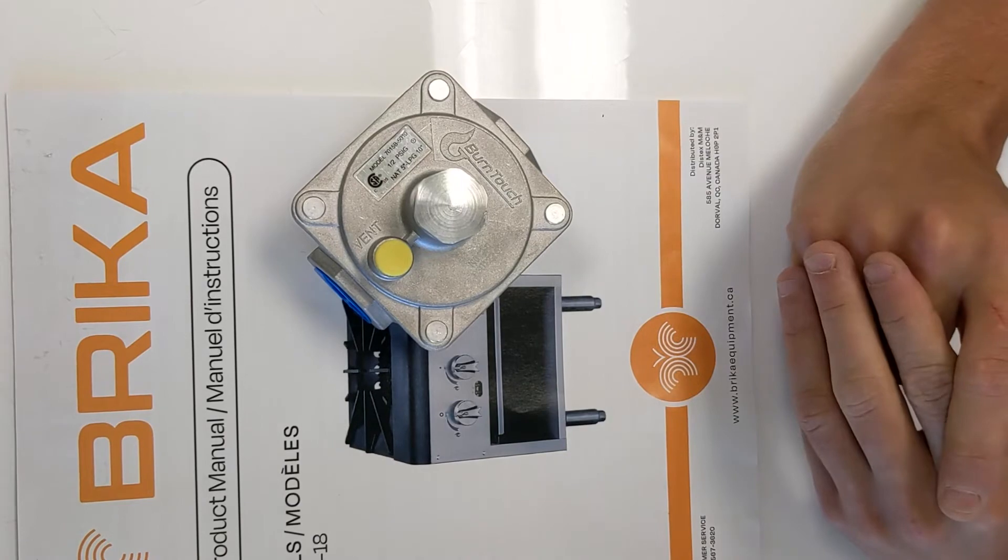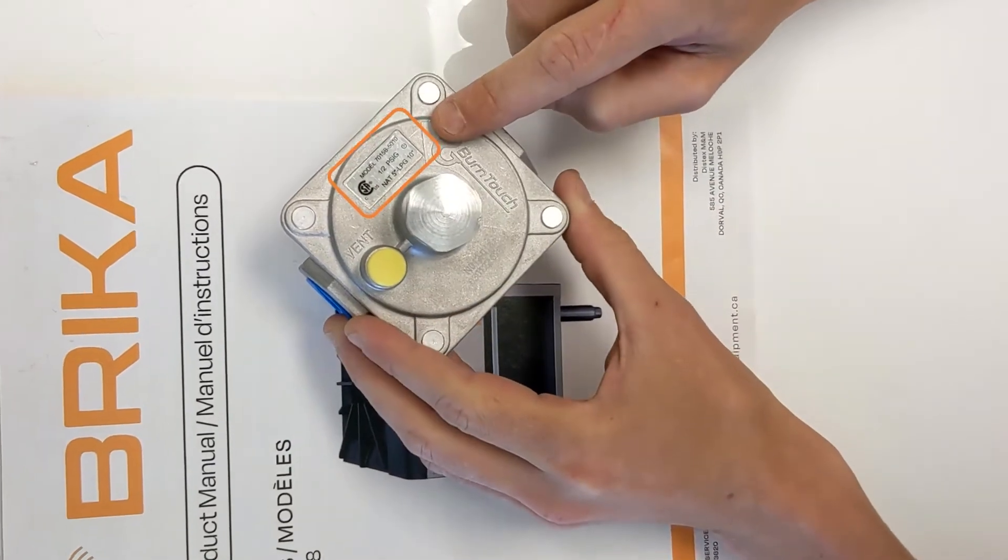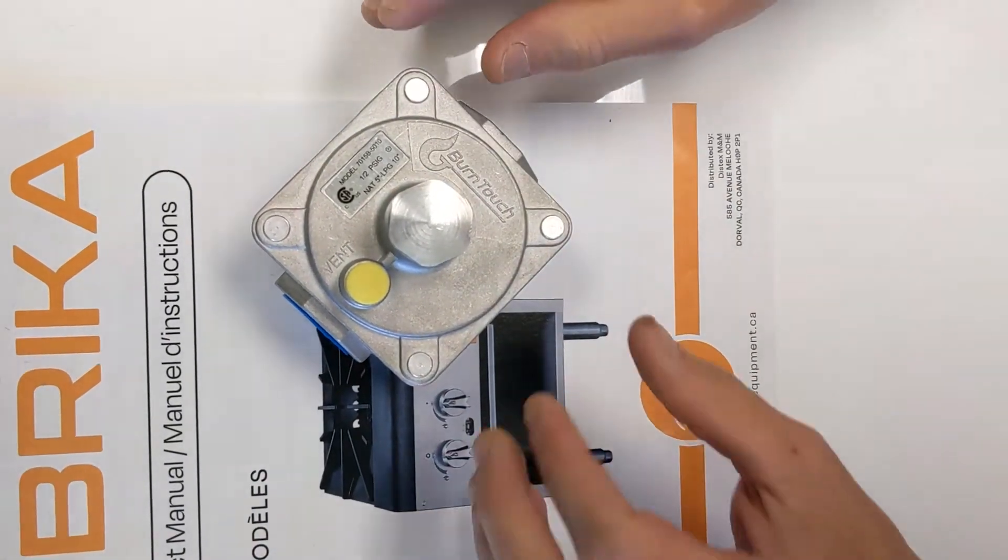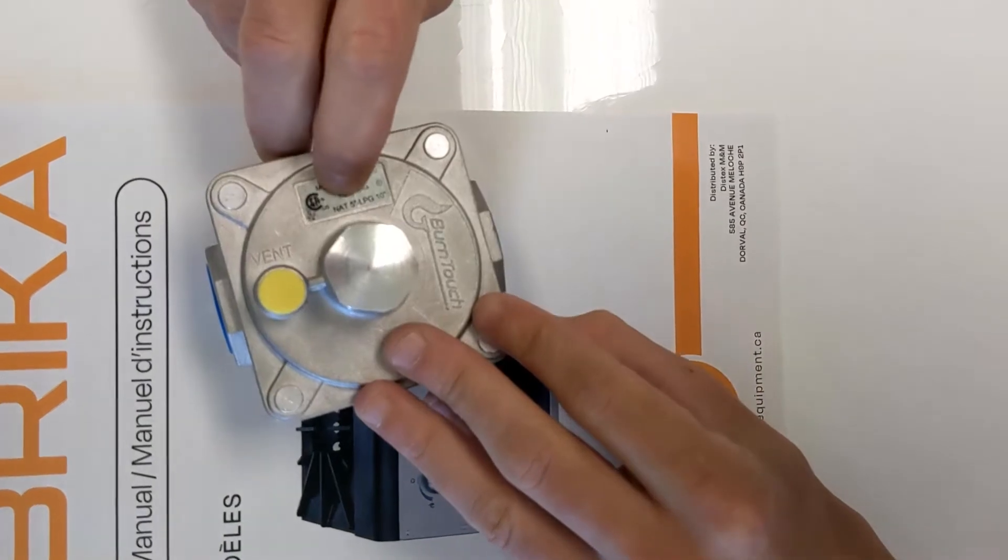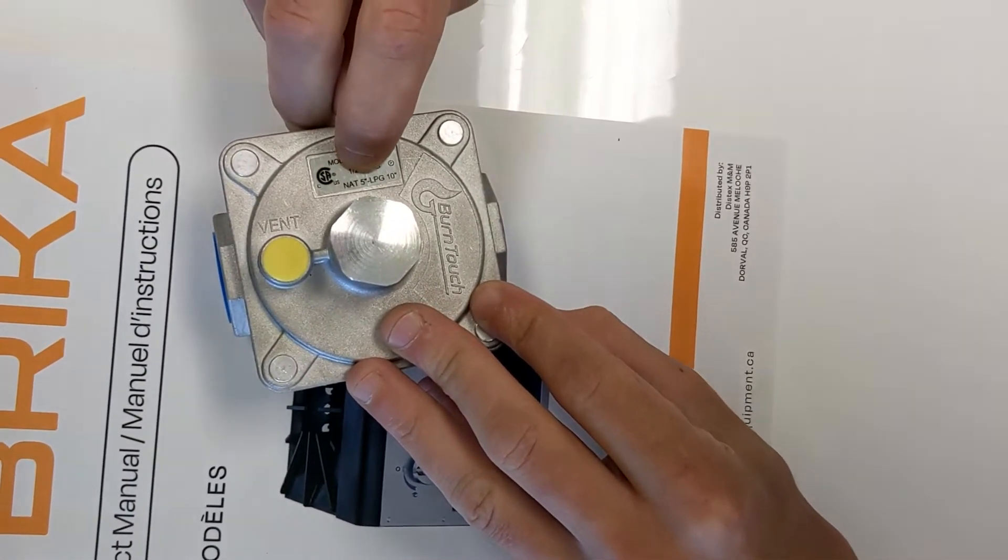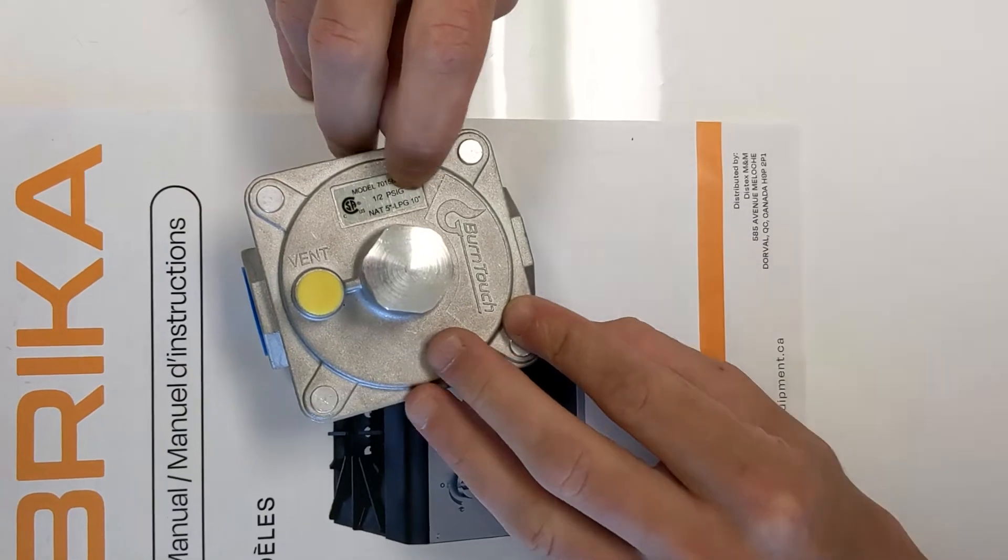But there's only one regulator supplied because our gas regulator is good for natural and propane. As we can see here on the gas regulator, it says natural 5 water columns and LPG 10 water columns.